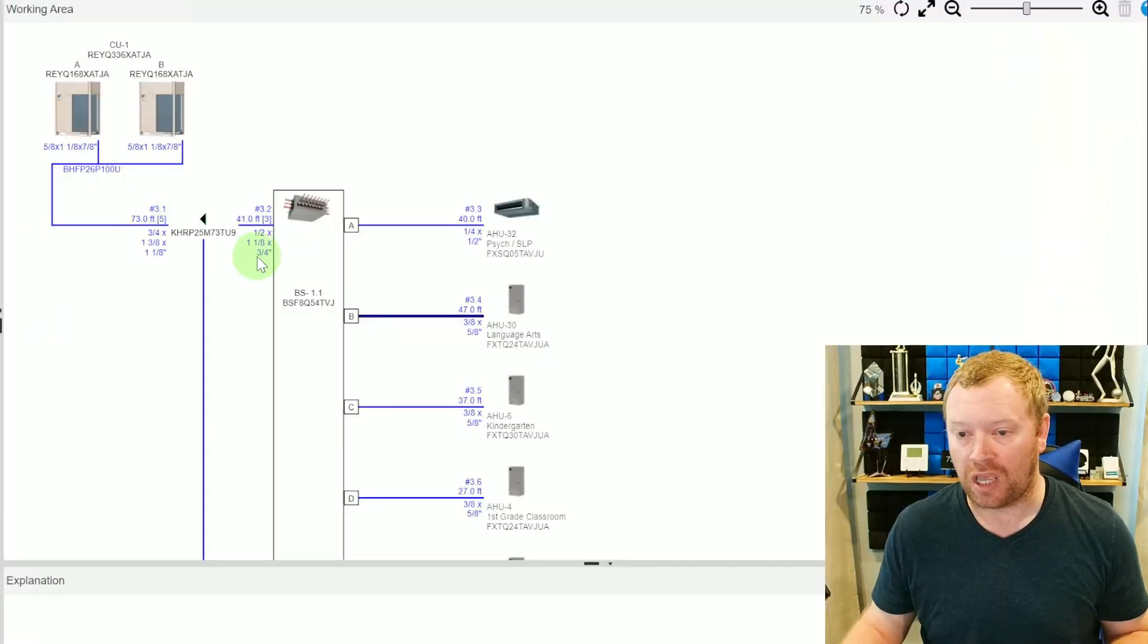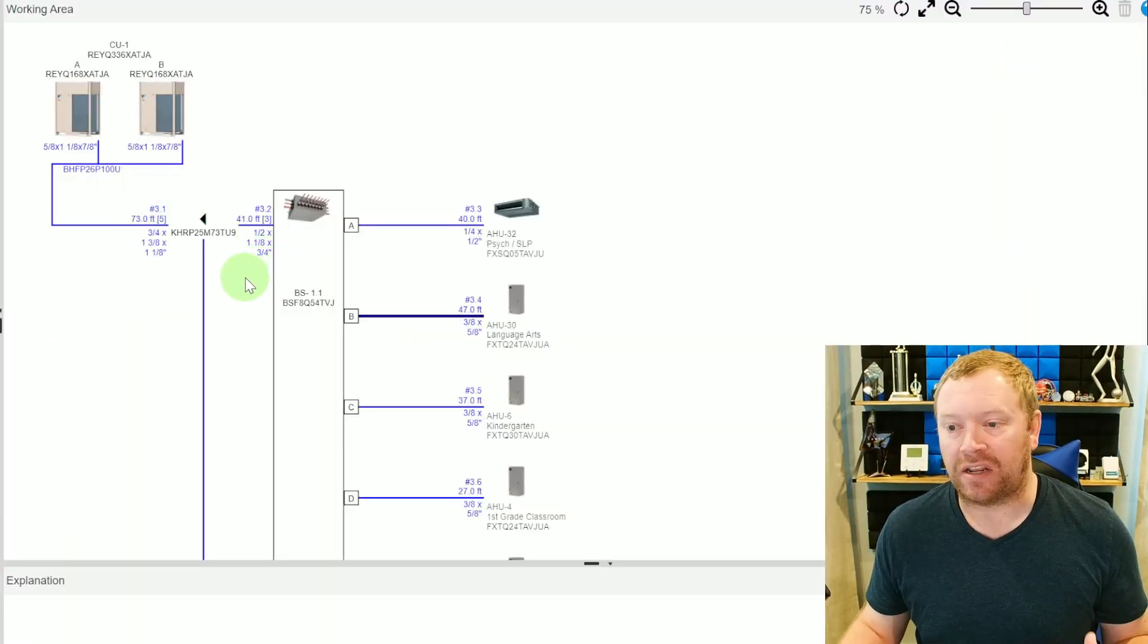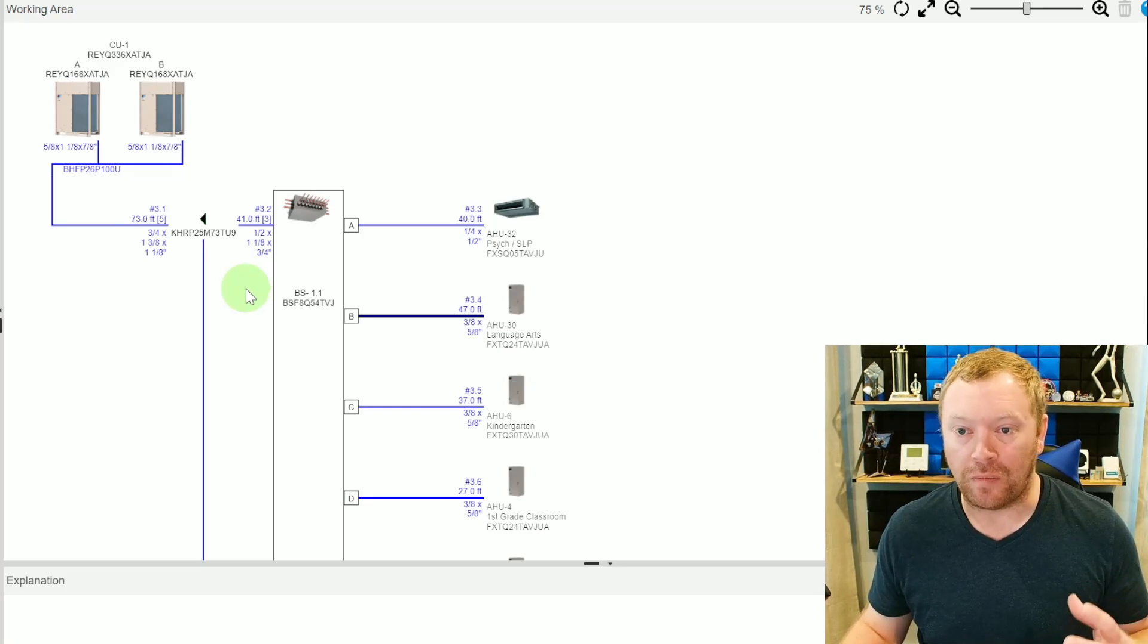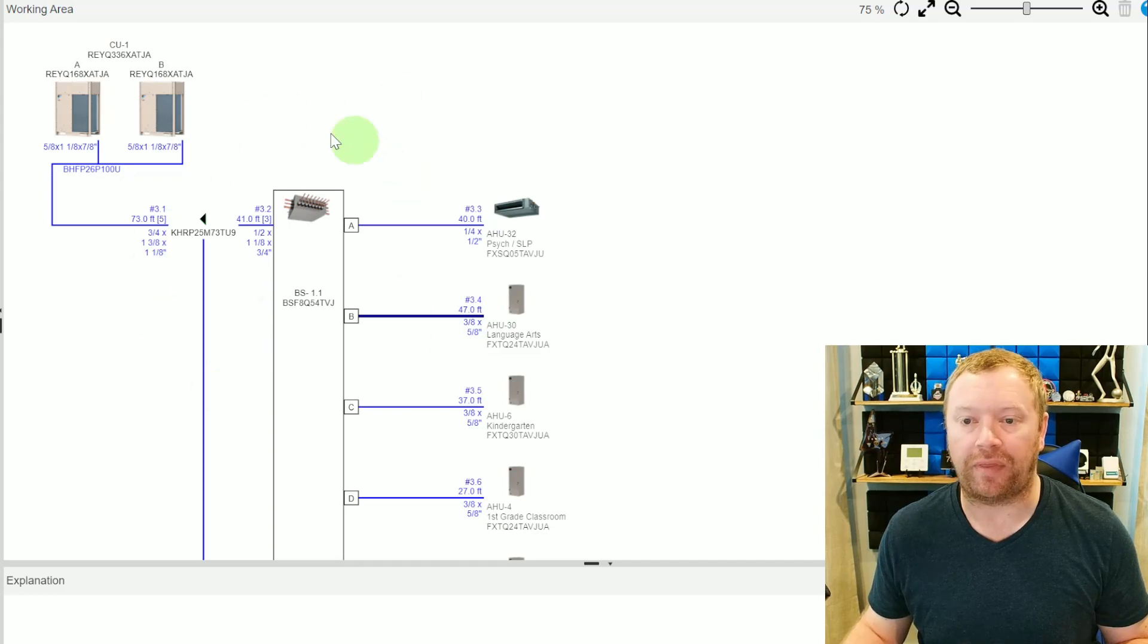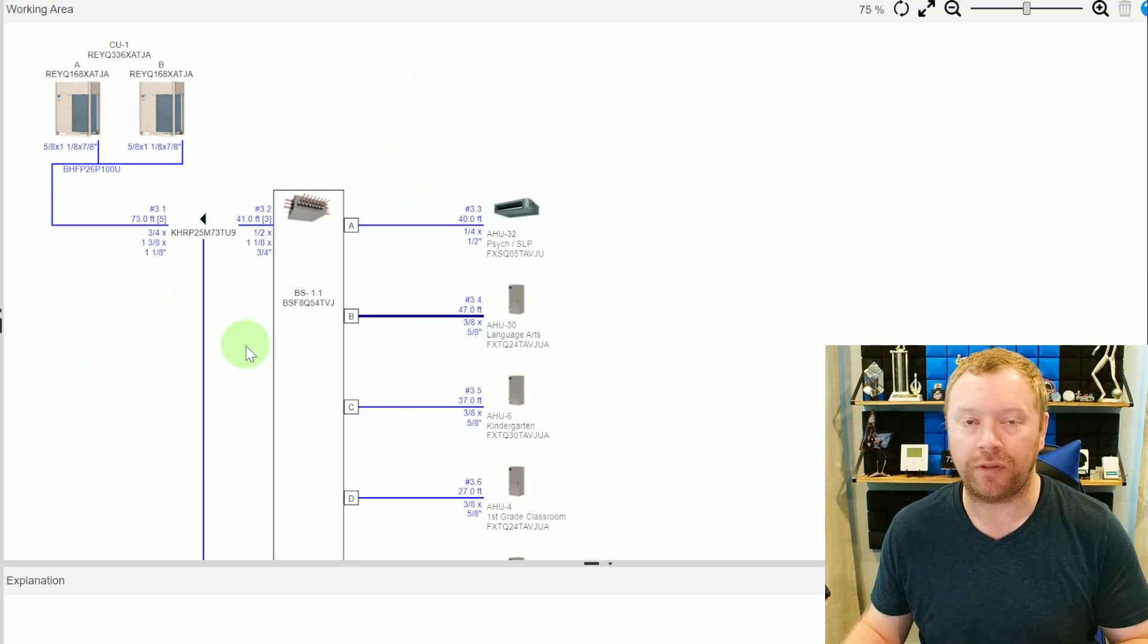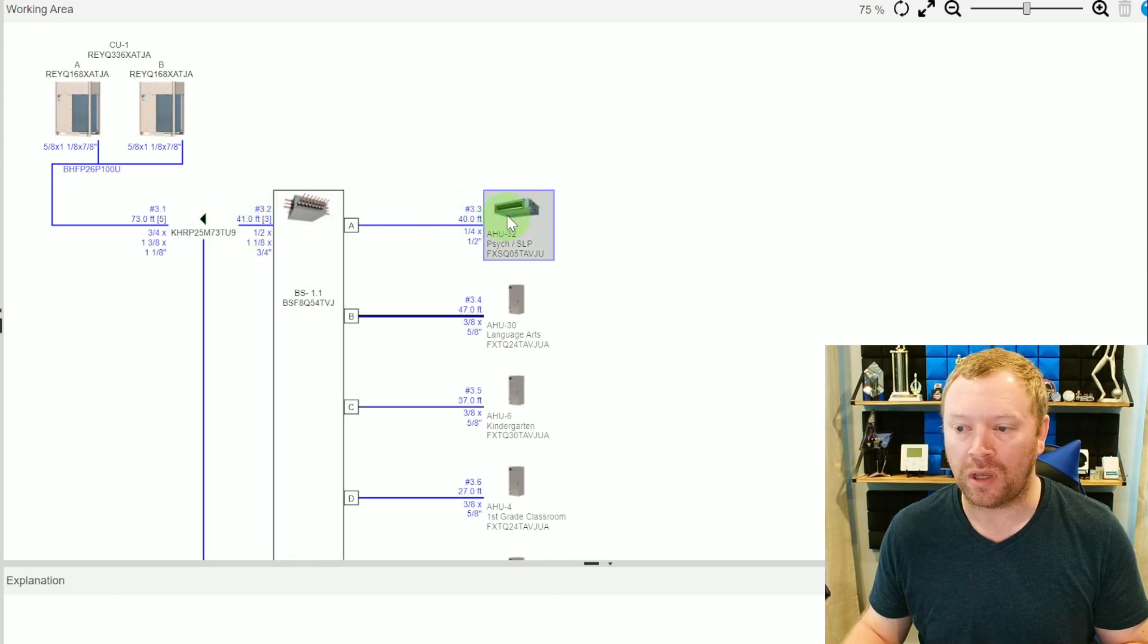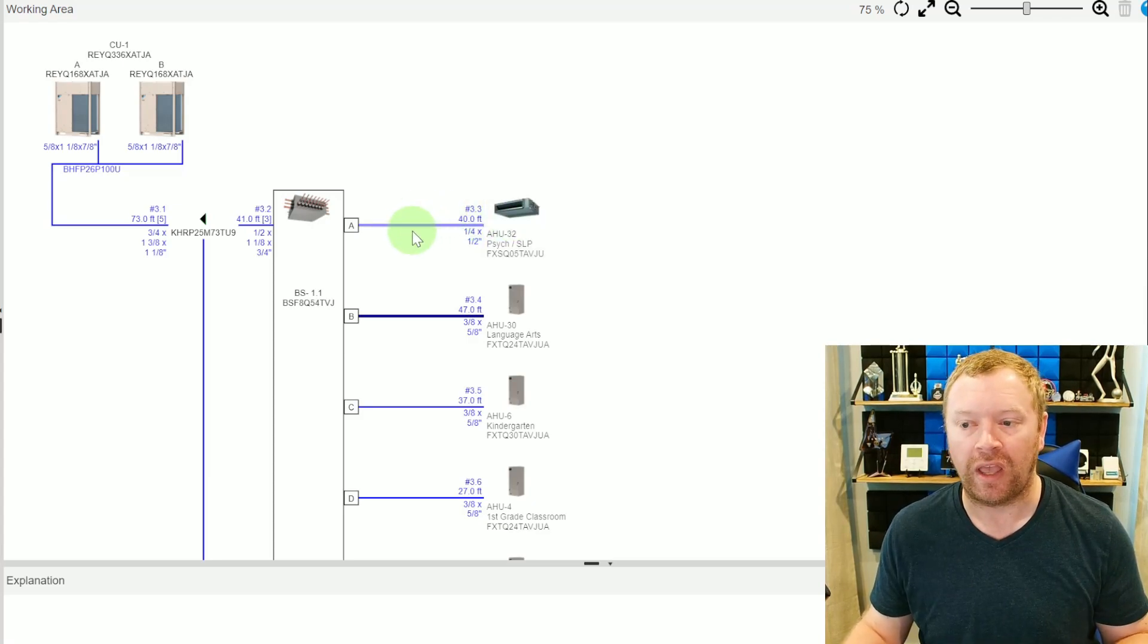On heat recovery systems, we're typically only changing the liquid line pipe size. And on heat pump systems, you will commonly have to change both the liquid and the gas pipe size. But we're again, not getting into all the details in today's video. I just want to show you guys a couple of things here because I can't stress again enough how important it is to have this be accurate. And the most accurate way you can do this is to mark up this actual print on the job site as you go, so that you can look at every single measurement from this length 41 plus this first indoor unit is 40, 81 feet. We're totally fine there.